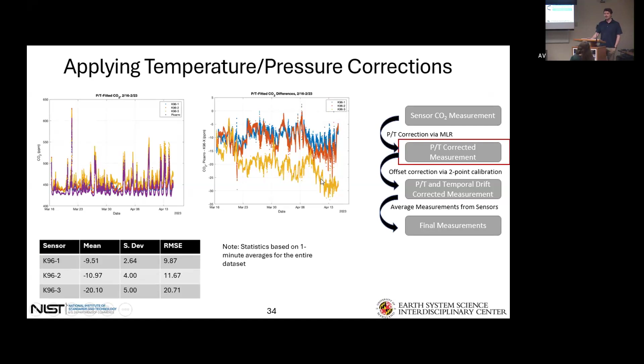So what happens when we do this? In this case, the P and T correction is done in real time. Every minute, a measurement comes in. If we look at it, we can see that this difference is largely gone. We are not 100 ppm off from our CRDS reference instrument, but we can still see this temporal drift, especially with sensor 3. And so that's why we need the reference gases. When we apply the reference gases, you can see that our RMSEs and standard deviations have drastically decreased. We can see that our three sensors follow the CRDS pretty well, though we can still see some noise in there.